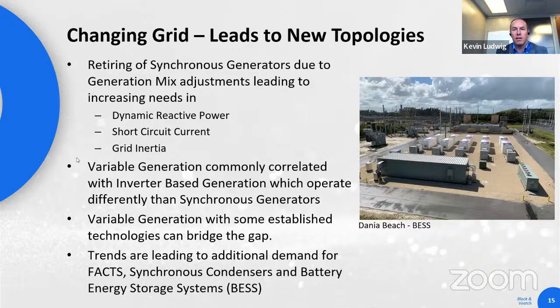So what we see is that we need to add some additional ingredients to the grid. Those ingredients include dynamic reactive power that we otherwise didn't need in the past, due to its inherent availability within synchronous generation. We also see a reduction in short circuit current, so we need to add that in, and we see a loss of grid inertia, so we have to look at how to add that ingredient back into the grid.